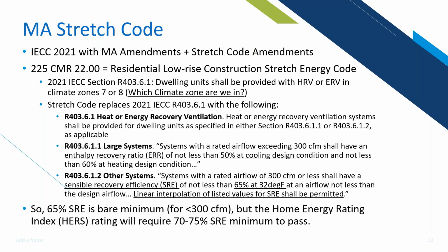Okay. Now, in a large system, which is 300 CFM or more, you must have an enthalpy recovery ratio, which is the first time we hear that term, and we'll talk more about it later. An enthalpy recovery ratio of not less than 50% in cooling design condition, and not less than 60% ERR in heating design condition. So that's for 300 CFM or more.